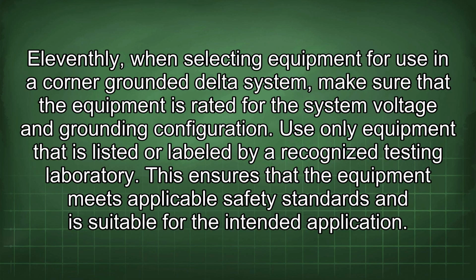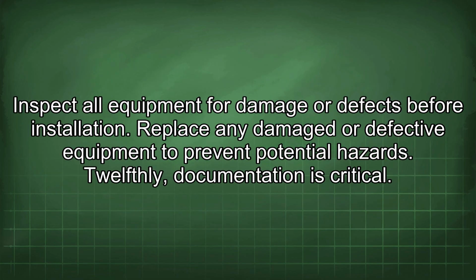11thly, when selecting equipment for use in a corner-grounded delta system, make sure that the equipment is rated for the system voltage and grounding configuration. Use only equipment that is listed or labeled by a recognized testing laboratory. This ensures that the equipment meets applicable safety standards and is suitable for the intended application. Inspect all equipment for damage or defects before installation. Replace any damaged or defective equipment to prevent potential hazards.